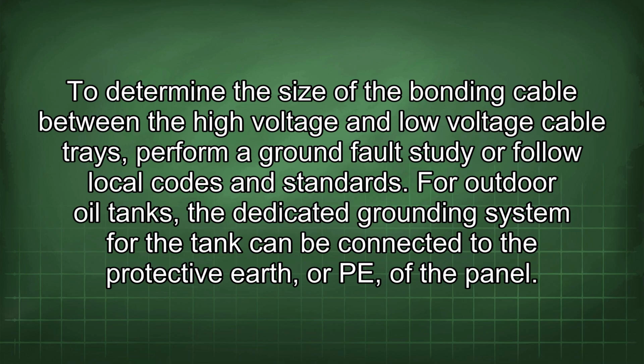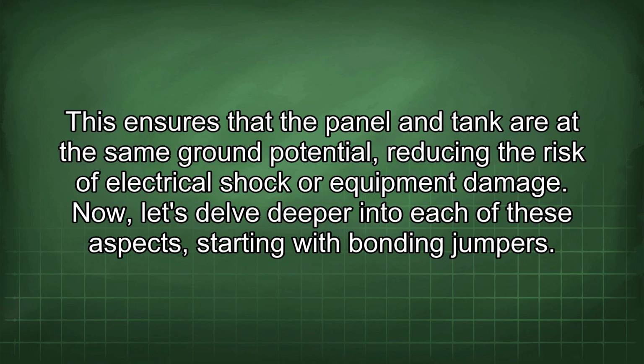For outdoor oil tanks, the dedicated grounding system for the tank can be connected to the protective earth, or PE, of the panel. This ensures that the panel and tank are at the same ground potential, reducing the risk of electrical shock or equipment damage. Now, let's delve deeper into each of these aspects, starting with bonding jumpers.